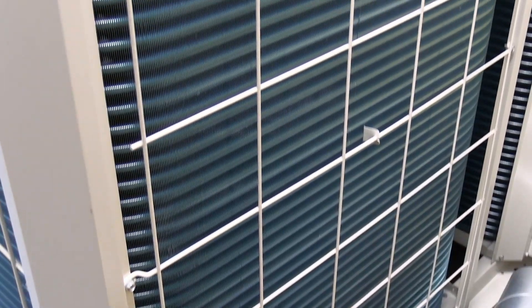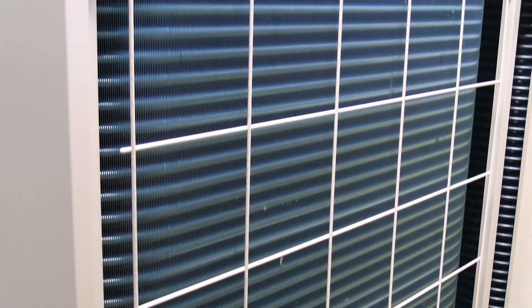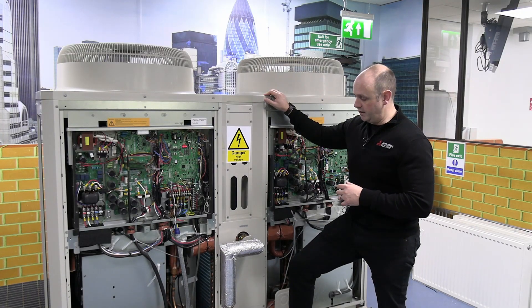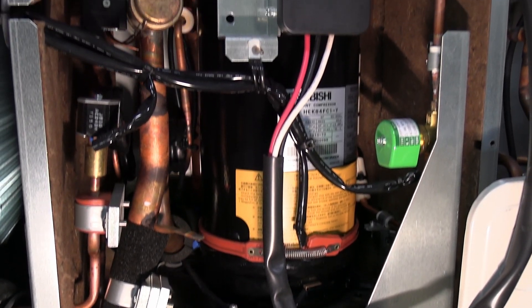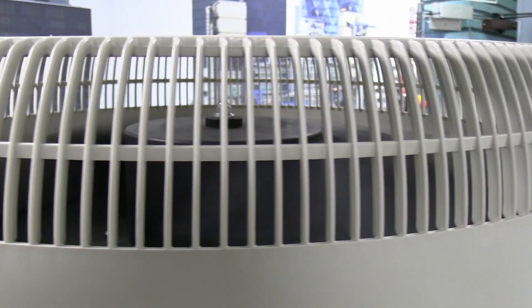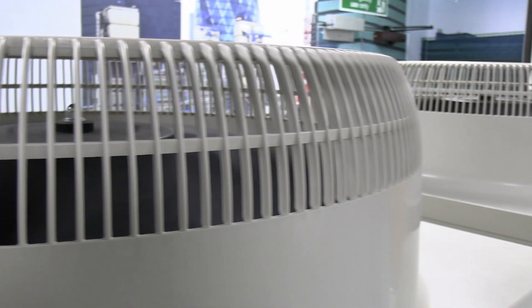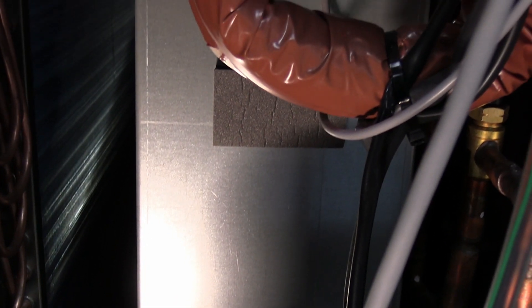We've got two sets of condensers, which are the wraparound coils you see around the actual unit. We've got two sets of compressors — they are scroll compressors and they're inverter driven, so they can ramp up and down to suit the needs of the system. The fan on top of the unit is also inverter driven, so that can ramp up and down to suit the needs of the evaporator. And there's a set of plate heat exchangers, so they're completely separate.